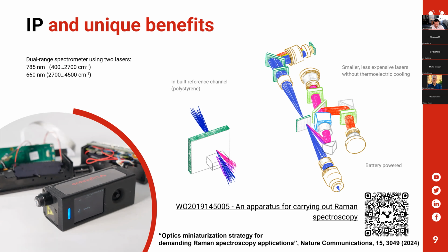miniRaman is protected by various international patents. As well, we have recently published a paper in Nature Communications where we describe the core principles of miniRaman technology. The key feature here is the presence of an inbuilt reference channel with a polystyrene sample. This allows us to use smaller, less expensive lasers without thermoelectric cooling. The spectrometer can be with one laser or with two lasers.